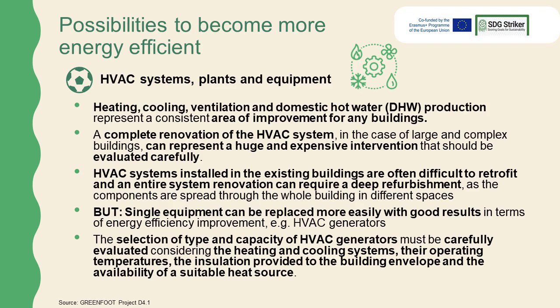Systems installed in existing buildings are often difficult to retrofit, and an entire system renovation can require a deep refurbishment as the components are spread through the whole building in different spaces. But single equipment can be replaced more easily with good results in terms of energy efficiency improvement. The selection of type and capacity of generators must be carefully evaluated, considering the heating and cooling systems, their operating temperatures, the insulation provided to the building envelope, and the availability of a suitable heat source.